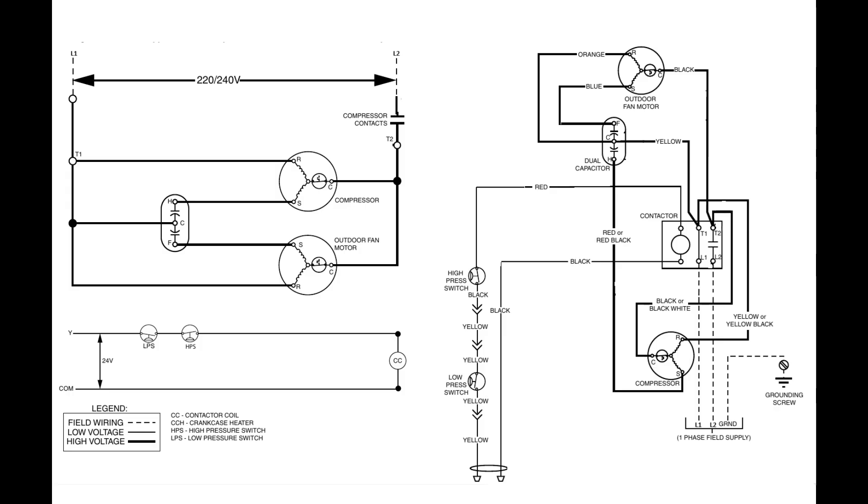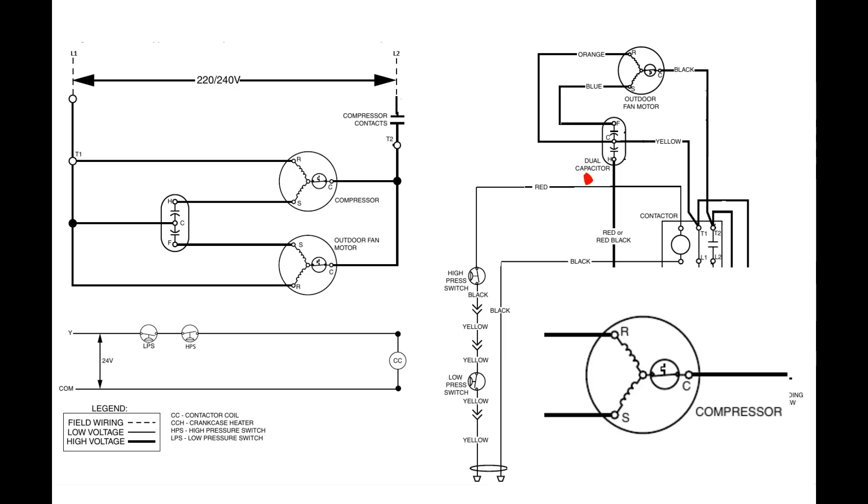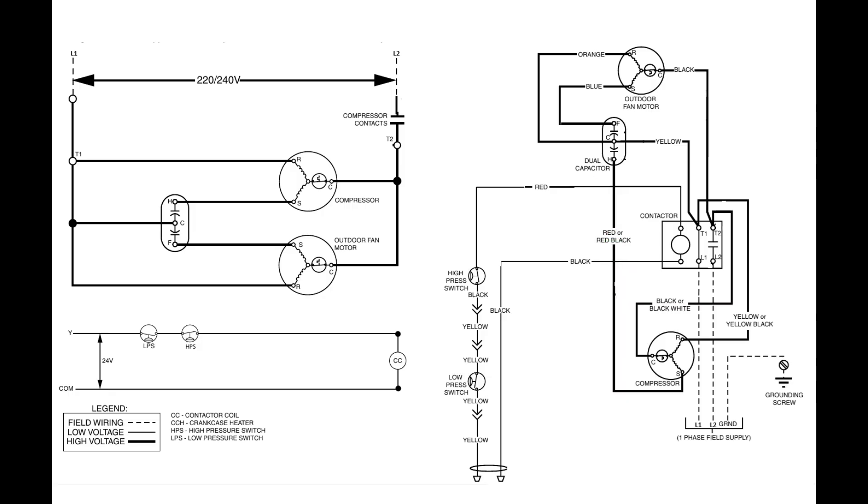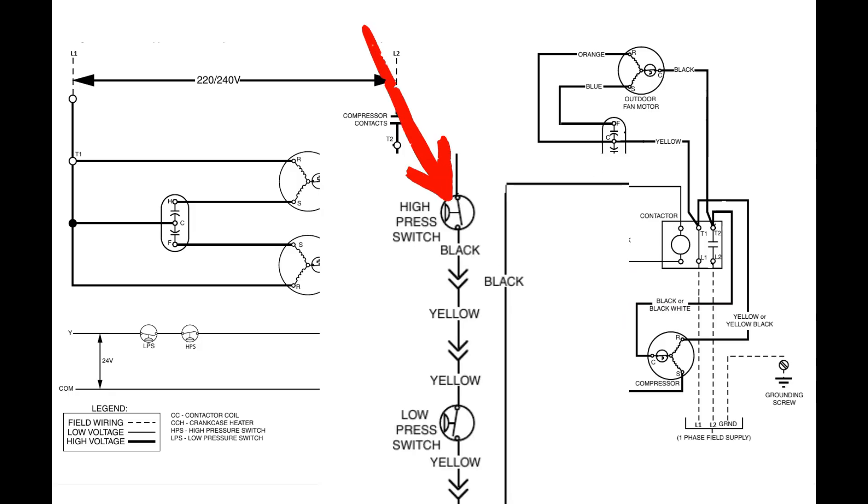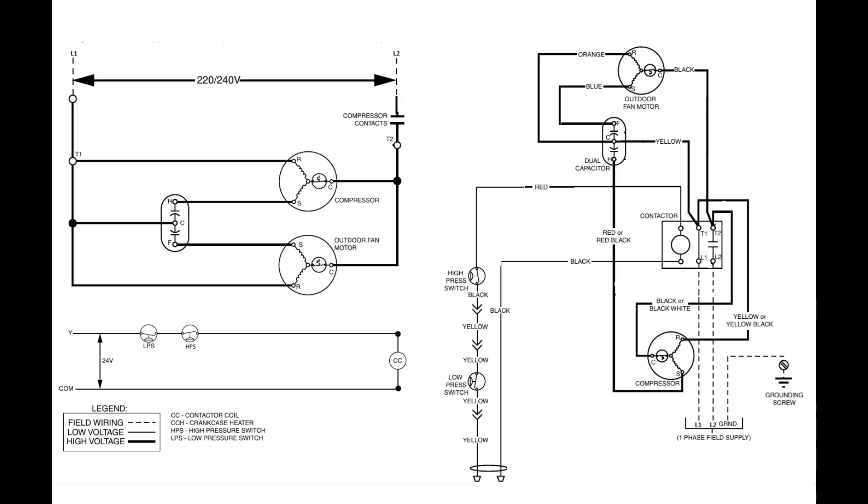So going back to our schematic, we can see all these things. We see a normally open switch on our contactor. We see a thermal overload switch in our compressor, which is normally closed. We see high and low pressure switches on our low voltage control circuit, which are also normally closed. We see male and female adapters connecting to one another. And we see intersections where wires are coming together where they are actually physically connecting and wires overlapping where they are not.